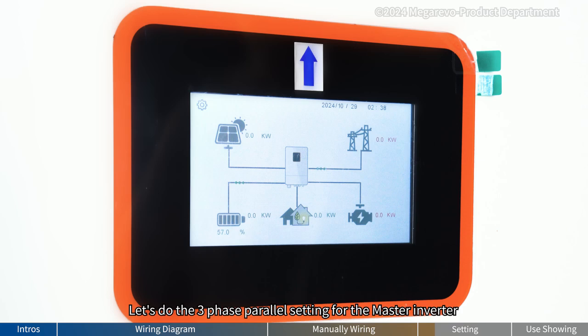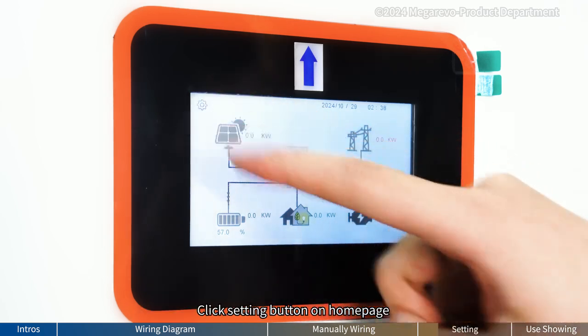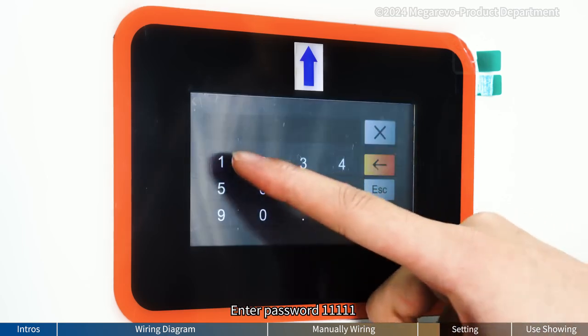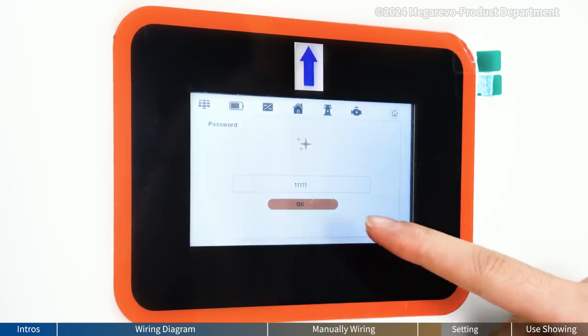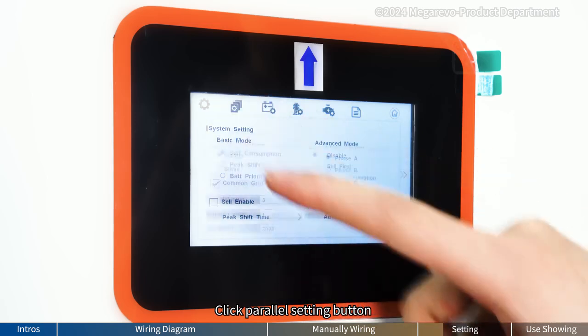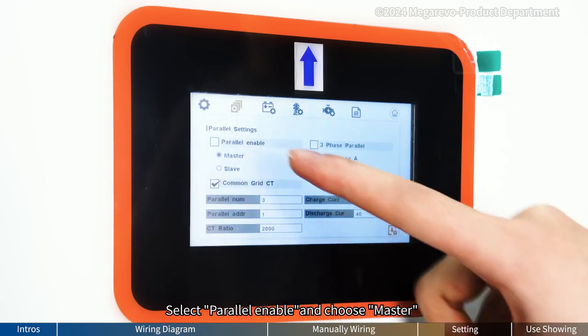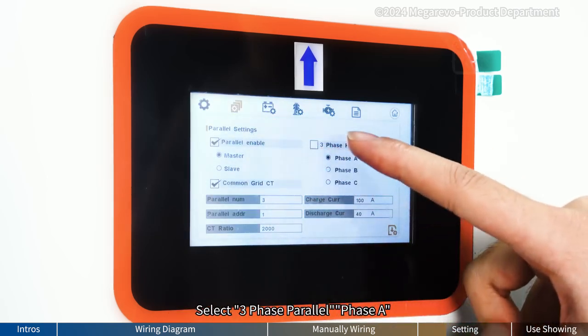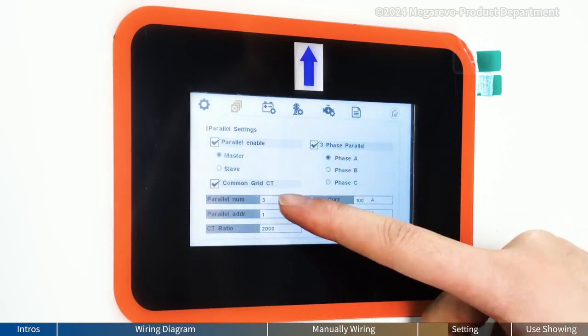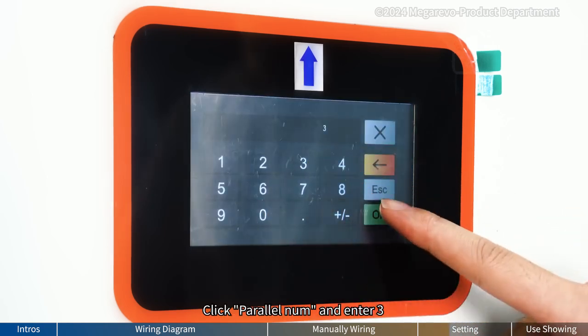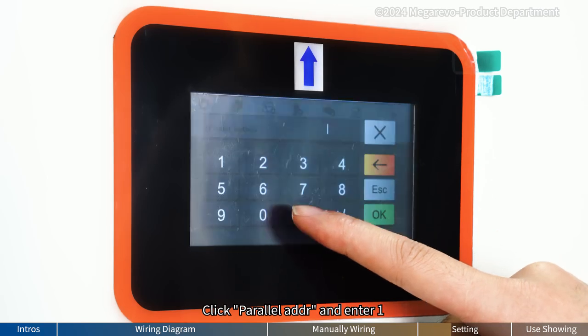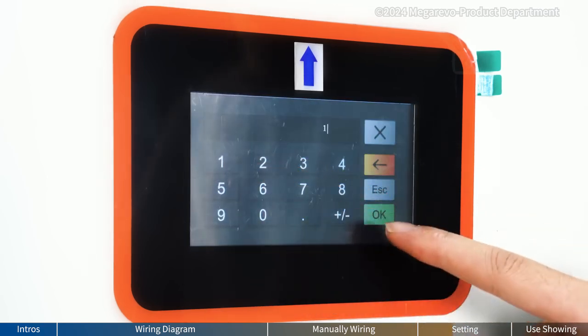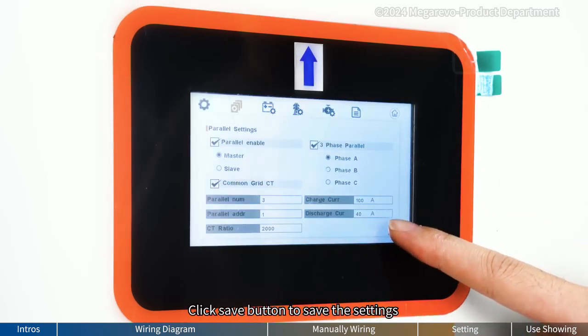Let's do the three-phase parallel setting for the Master inverter. Click Setting button on homepage. Enter password 11111. Click Parallel Setting button. Select Parallel Enable and choose Master. Select three-phase parallel, phase A. Click Parallel Number and enter 3. Click Parallel Address and enter 1. Click Save button to save the settings.